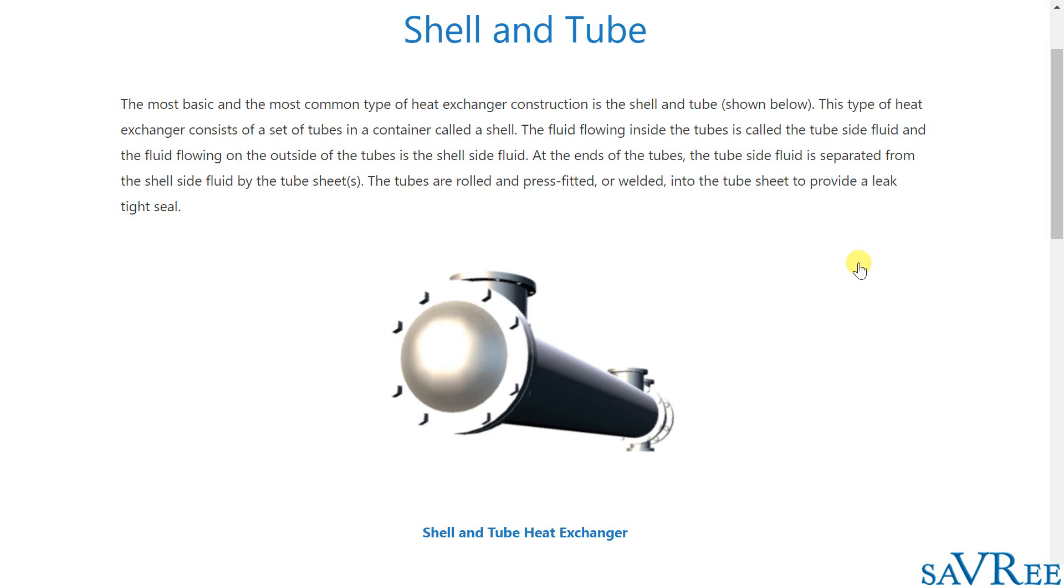The fluid flowing inside the tubes is called the tube side fluid and the fluid flowing on the outside of the tubes is the shell side fluid. At the end of the tubes, the tube side fluid is separated from the shell side fluid by the tube sheets. The tubes are rolled and press fitted or welded into the tube sheet to provide a leak tight seal.